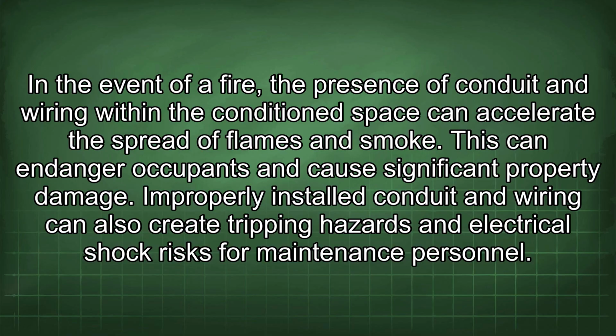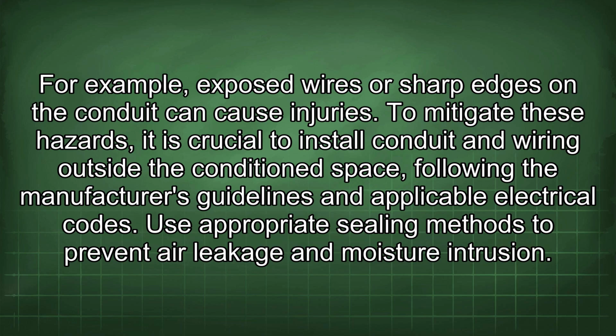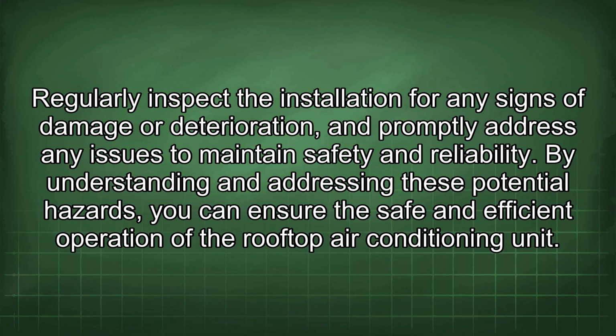Improperly installed conduit and wiring can also create tripping hazards and electrical shock risks for maintenance personnel. For example, exposed wires or sharp edges on the conduit can cause injuries. To mitigate these hazards, it is crucial to install conduit and wiring outside the conditioned space, following the manufacturer's guidelines and applicable electrical codes. Use appropriate sealing methods to prevent air leakage and moisture intrusion. Regularly inspect the installation for any signs of damage or deterioration, and promptly address any issues to maintain safety and reliability. By understanding and addressing these potential hazards, you can ensure the safe and efficient operation of the rooftop air conditioning unit.